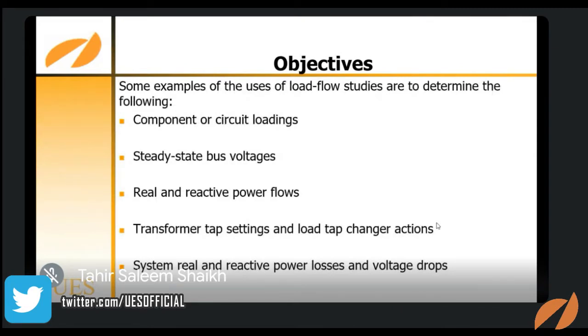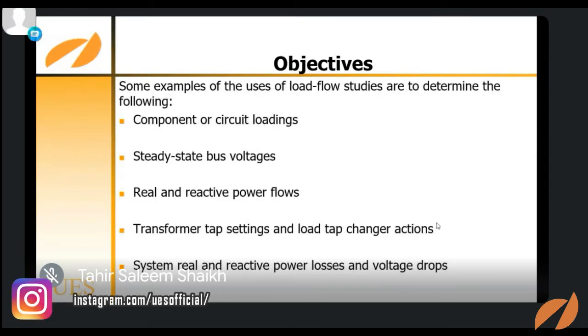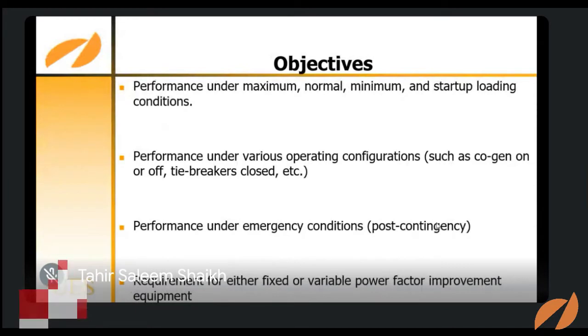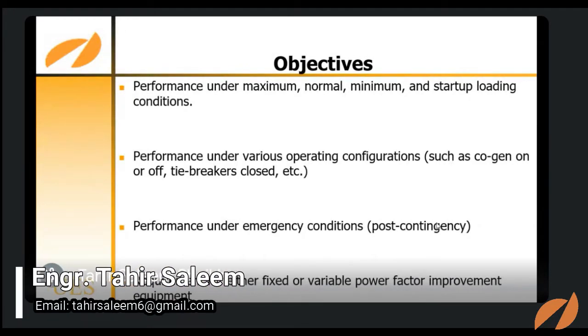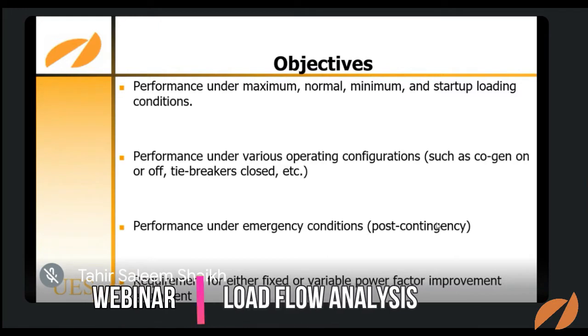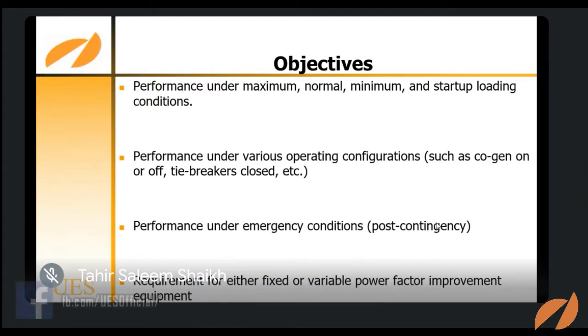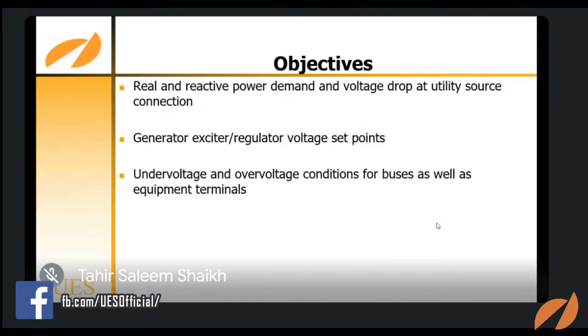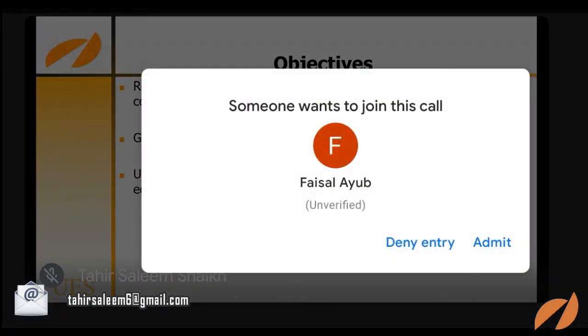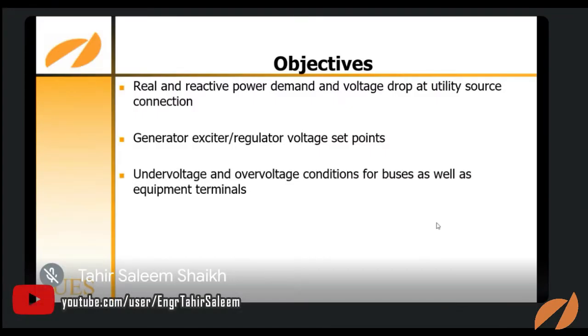Some examples: component or circuit loading, steady state bus voltage, real and reactive power flows, transformer tap settings and load tap changer action, system real and reactive power losses and voltage drops, performance under maximum, normal, minimum and startup loading condition, performance under various operating conditions such as cogen on or off, tie breaker close, etc., performance under emergency condition, requirement of either fixed or variable power factor improvement equipment, real and reactive power demands and voltage drop at utility source connection, generator exciter, regulator voltage set point, under voltage and over voltage condition for buses as well as equipment terminals.